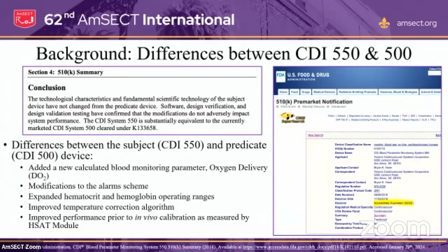So the differences are, there are a few. They added a new calculated blood monitoring parameter, DO2, and they modified the alarm scheme. They expanded the hematocrit and hemoglobin operating ranges. They improved the temperature correction algorithm, and they improved the performance prior to in vivo calibration as measured by the HSAT module. Interestingly, since this was deemed substantially equivalent, it did not require any animal or clinical validation studies.